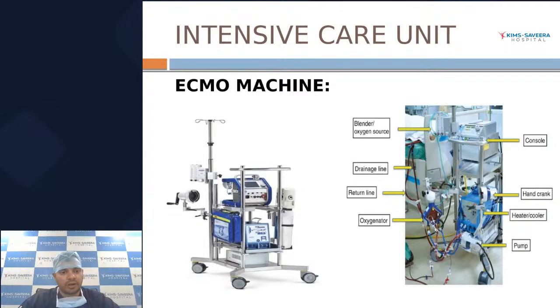So next, another important machine which has come to the forefront after the COVID pandemic is the ECMO machine. So what is ECMO? ECMO is extracorporeal membrane oxygenator. So what this machine does basically, you have seen a ventilator. So what does a ventilator do? A ventilator is sending in oxygen and bringing out carbon dioxide. So till one level, when lungs are functioning fine, or lungs are doing a good exchange of oxygen and carbon dioxide, then the ventilator can be continued.